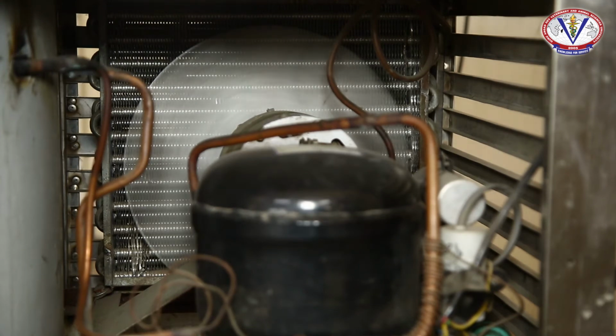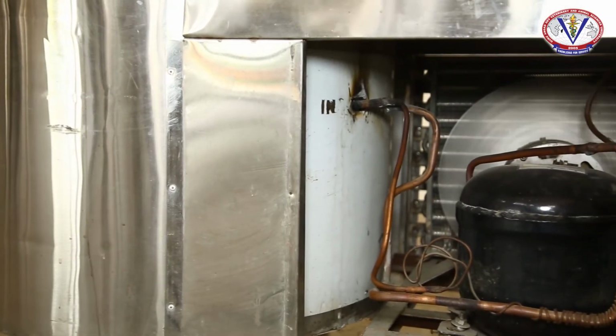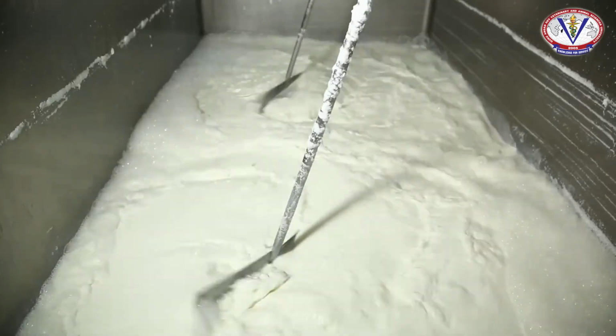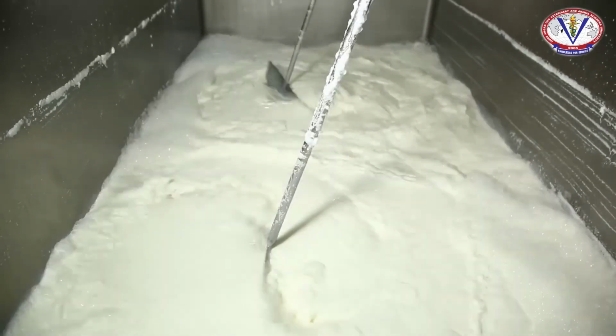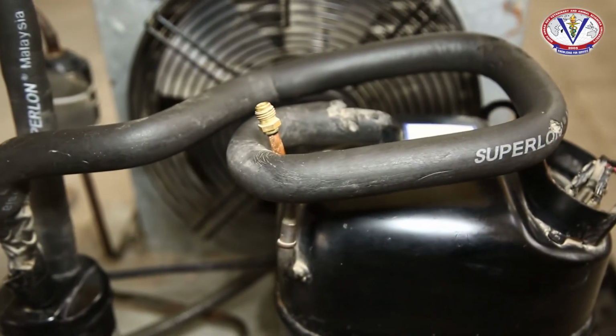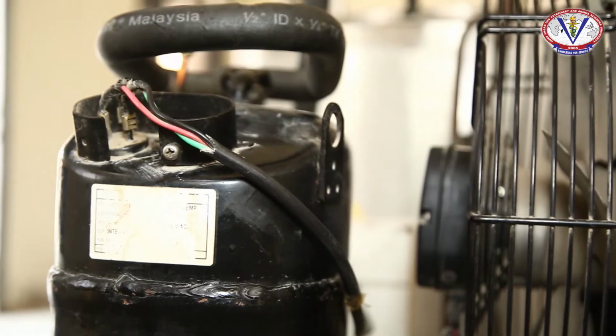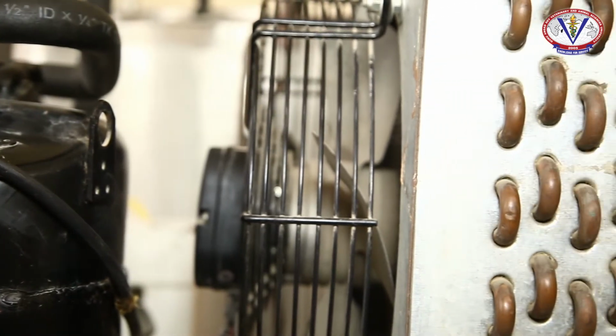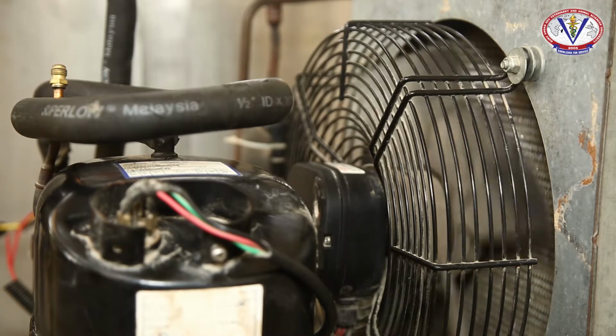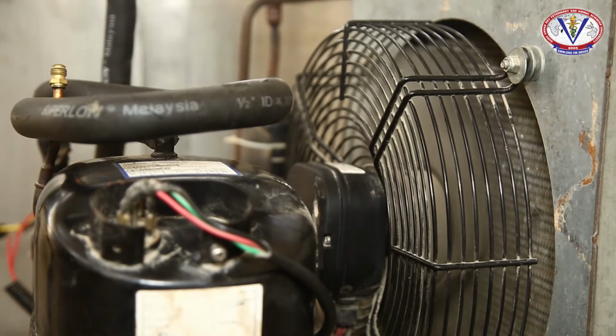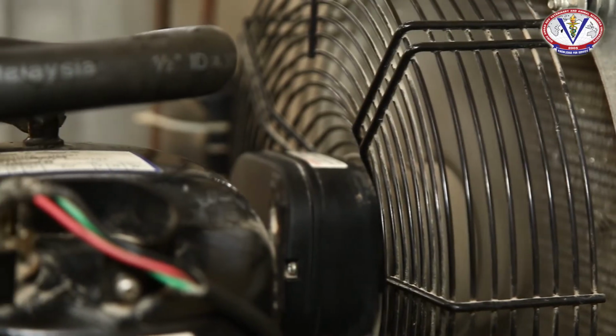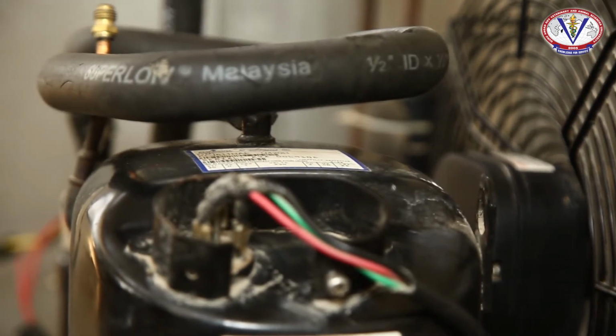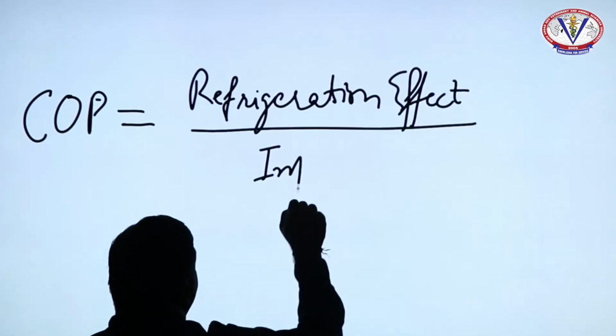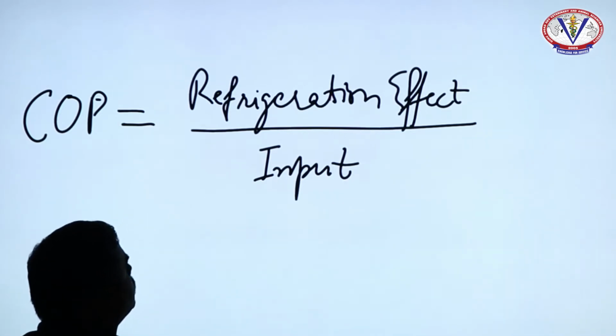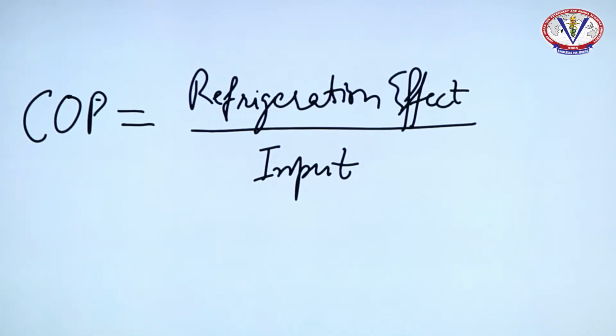The heat to be released by the condenser consists of two components. One component is the heat that is taken by the refrigerant in the evaporator, and the second is the heat which is added during the compression process, and this sum total heat has to be released by the condenser. So the condenser must be designed in such a way that it should keep on transferring heat and the whole of the refrigerant vapor should be converted into liquid form. The main aim, as shown on this pH diagram, is that we have to follow the liquid line to maximize the COP, or the maximum effect that we can get out of that particular designed refrigeration system.